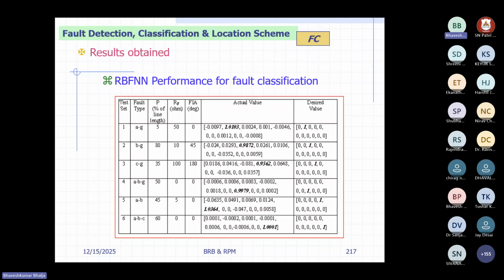Now, if you look at B to ground fault, C to ground fault, serial number 2, 3, 4, 5, 6, at serial number 2 the actual value is 0.98 or 0.99, and the desired value is 1. Similarly, at serial number 3, the actual value is 0.96 and the desired value is 1. At serial number 4, double line to ground fault, the actual value is 0.99 and the desired value is 1, and so on for other cases. So you are not always getting 1; you may get slightly below 1 or slightly higher than 1. So whenever you decide your desired value, you have to give a range. Let's say if it is between 0.95 and 1.05, then I consider this as A to ground fault, like that.